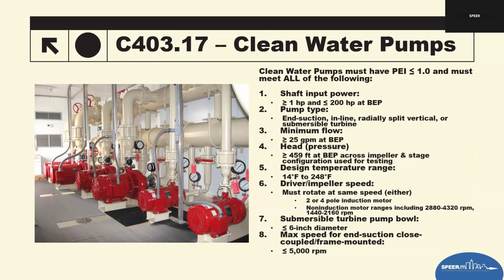Only pumps with a pump energy index, PEI, not greater than 1 are allowed, meaning the pump must be at least as efficient as the federal baseline. The key performance requirement is that this applies only to pumps from 1 to 200 horsepower, which covers the majority of commercial hydronic circulation pumps.